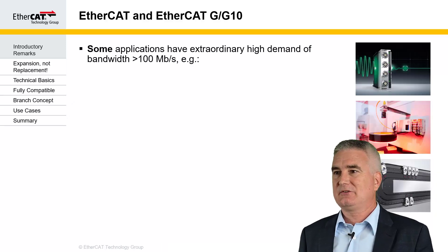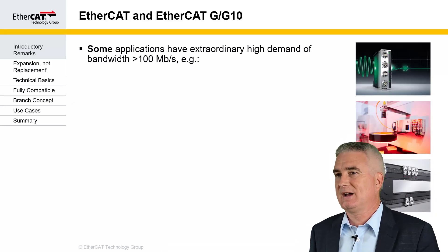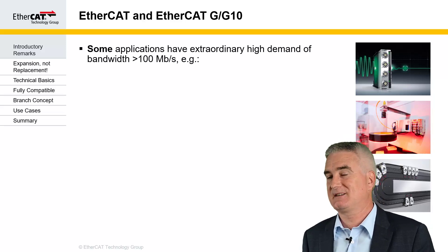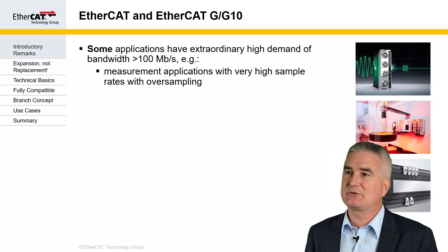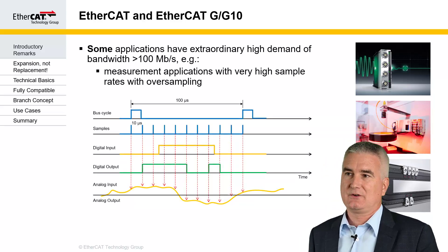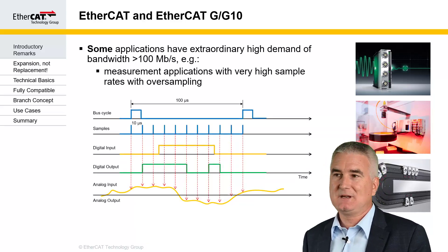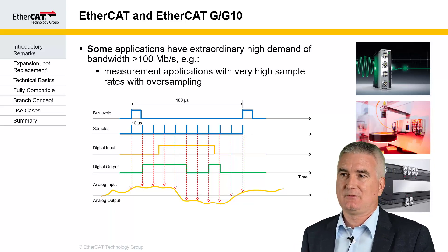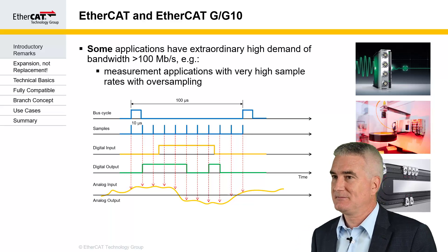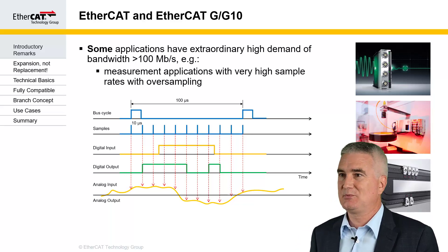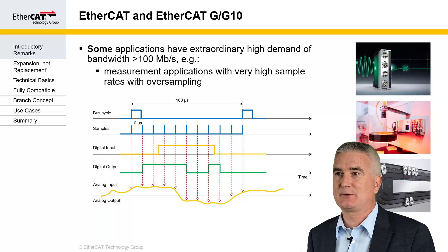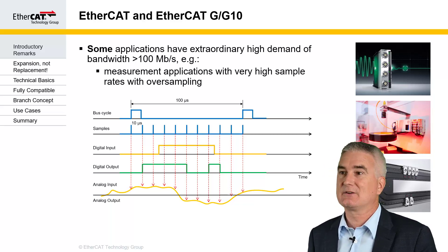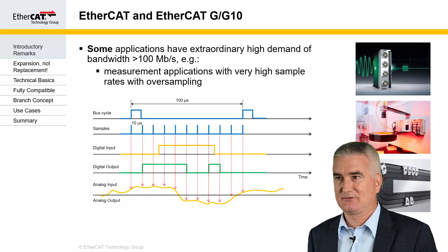However, some applications have an extraordinarily high demand of bandwidth that exceeds the 100 megabit that EtherCAT can provide today. One example is measurement applications with oversampling. That means, for instance, an analog input is sampling multiple times for every communication cycle. And we have analog inputs today that sample at 300 kHz with 24-bit resolution and multiple channels. You can imagine that this requires a lot of bandwidth.